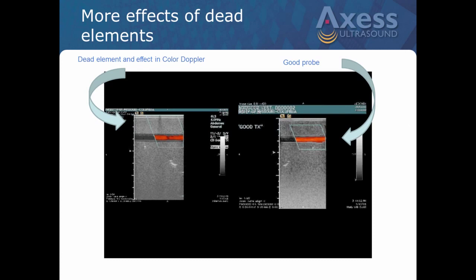Here are some more effects of dead elements, this time in color -- remember this is color Doppler. To the left, we simulated a dead element, and again there's an effect in the color Doppler. This is being done on a phantom, but if you were looking at this on a patient, the reading physician might suspect some sort of blockage because you're not seeing color through here, and might think there's plaque buildup or something in the artery. Over here is what it looks like in a normal, good probe with all elements firing.